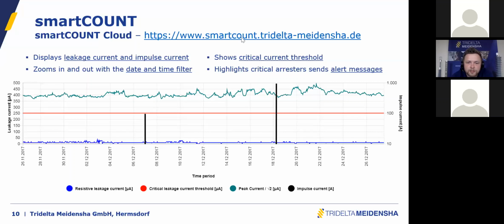And last but not least, we have those black bars you can see. This is the discharge current. We have one discharge current here with 100 amps and one with 1000 amps. You can see on the right axis of the diagram the values of those black bars, and of course they are placed on the date, or maybe also on the date and time, of the timeline of this diagram. So you see not only the amplitude, not only the surge count, you also see the date and time when it occurred in this diagram.